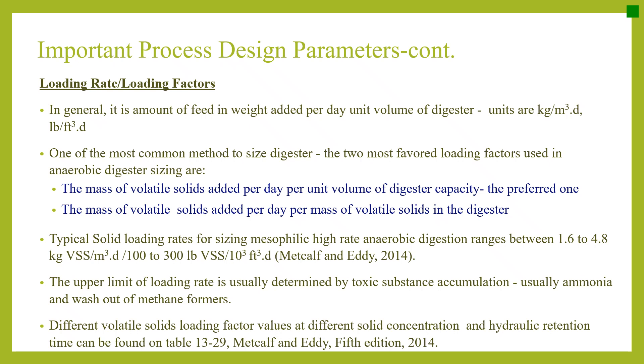The upper limit of loading rate — the maximum amount of feed that can be added to the digester — is usually determined by toxic substance accumulation, typically ammonia, and also washout of methanogens. If we add more feed we have to remove more effluent, which may prevent the methanogenic population from growing, resulting in washout. Different volatile solid loading factor values at different solid concentrations and hydraulic retention times can be found in Table 13-29 in Metcalf and Eddy, 5th edition.